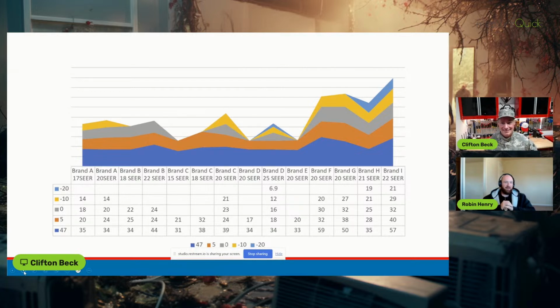I don't want to throw spaghetti at the wall and see what sticks. I want to do the math, validate it, and trust the math. Because more often than not, when somebody approaches you saying, 'I want a heat pump, my buddy said I need a 3-ton for my one-room addition,' you have to say, let's have a conversation. Every single one of them is very, very critical. If nothing else, you've got the math to fall back on, rather than just taking a stab at it.